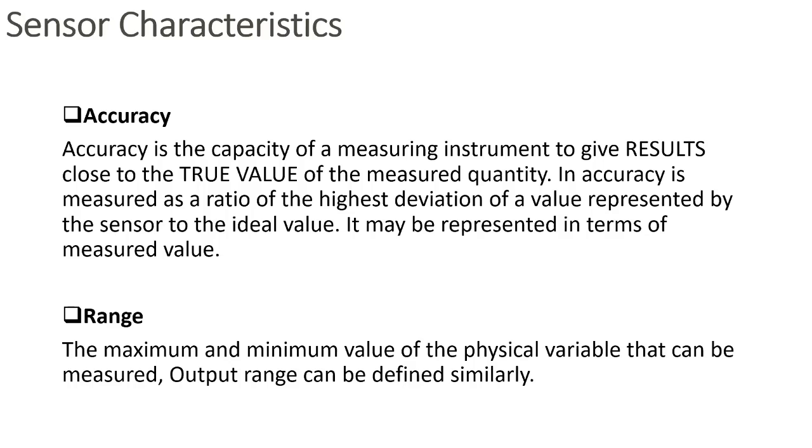That means if I am measuring the temperature, how close is it to the real temperature? Because what you are doing is converting this physical phenomenon into a digital signal. If you cannot do that at least to a value close to the real value, there's no use in doing it. So you are going to focus on accuracy a lot, but there can be deviations. It's okay. As an example with temperature, if the temperature is 25.123 Celsius in the real world, and the sensor is measuring 25.1, that's also acceptable for your application.